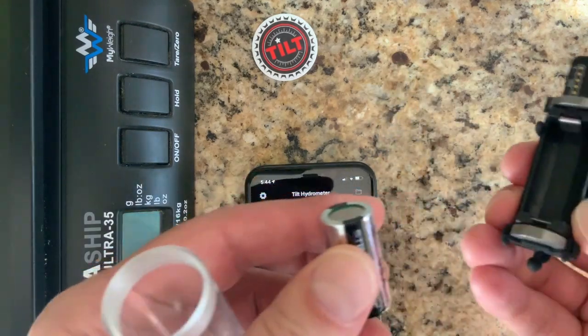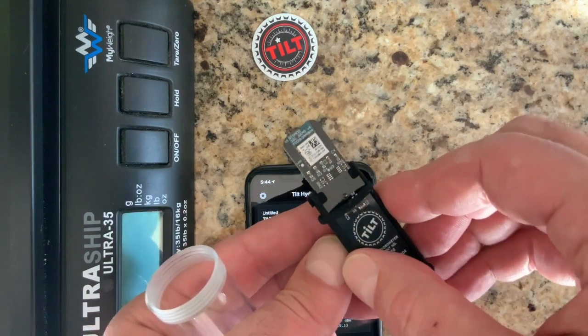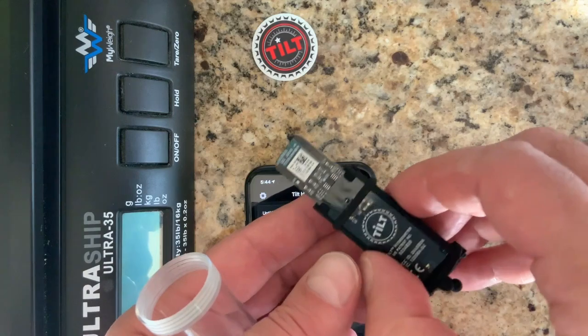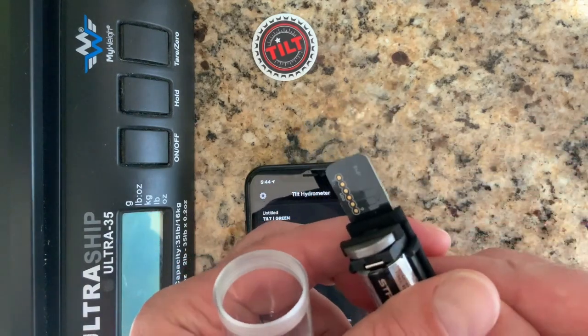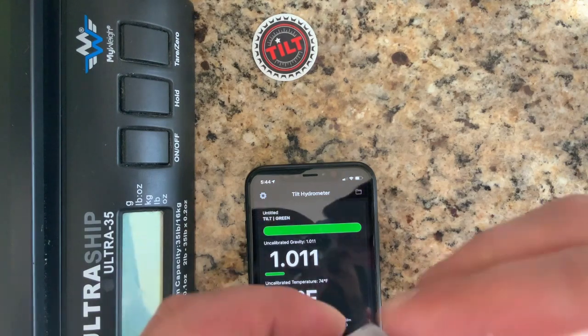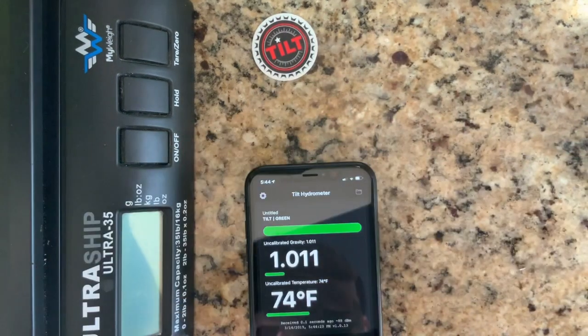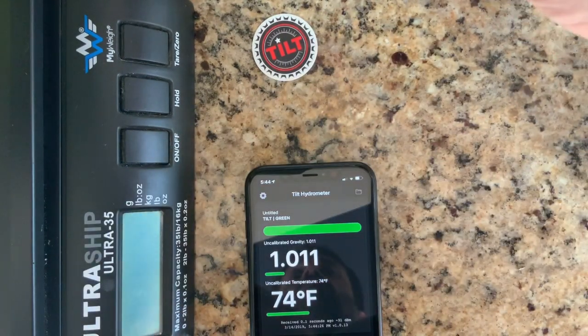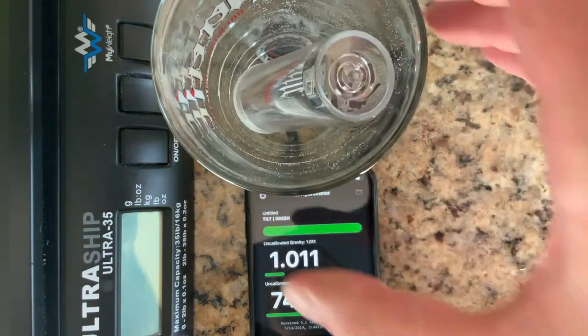I'm going to pull the battery out and replace it. You'll see the LED flash a violet color. I'm going to insert it into the Tilt case, tighten the cap, and float it in a pint glass to calibrate or zero in water.